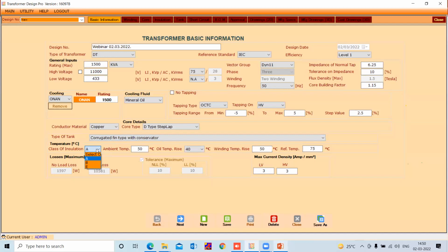Corrugated fin is the one you have chosen here. The class of insulation can be chosen as A, B, or E. The ambient temperature maximum can be set. The oil temperature rise can be selected from the list given here. Winding temperature rise can be selected or edited here, 50 degrees, whatever you wish to set. The reference temperature can be set here.